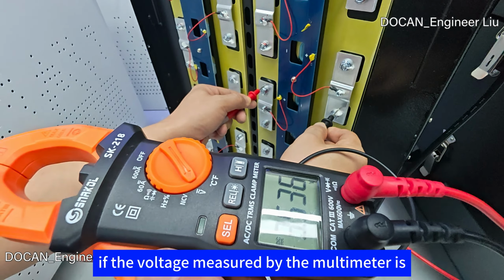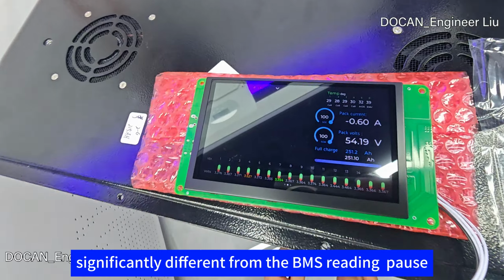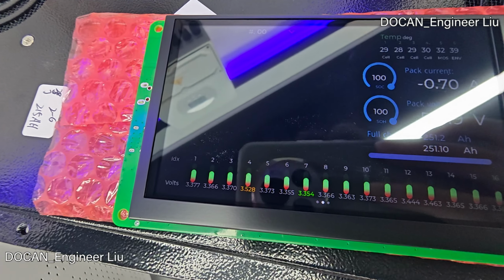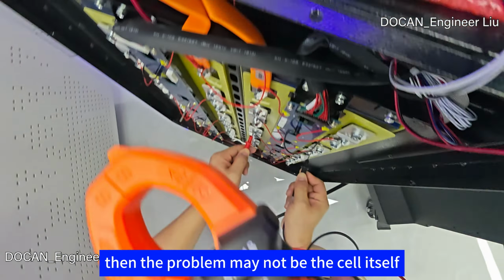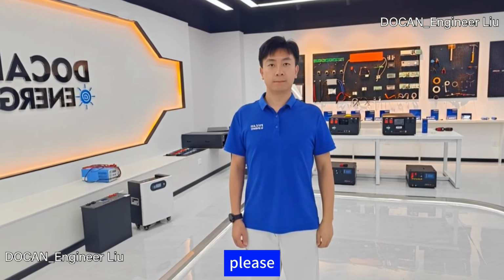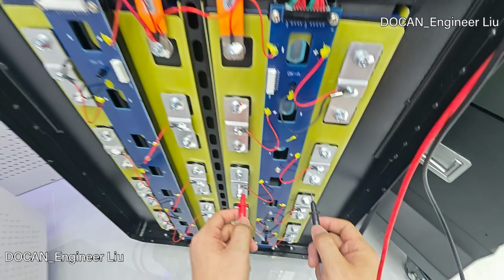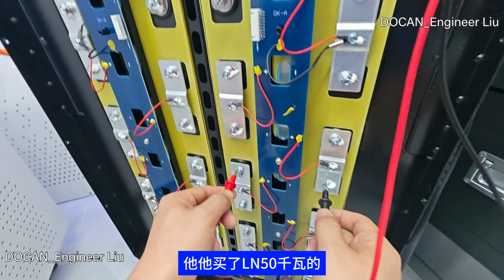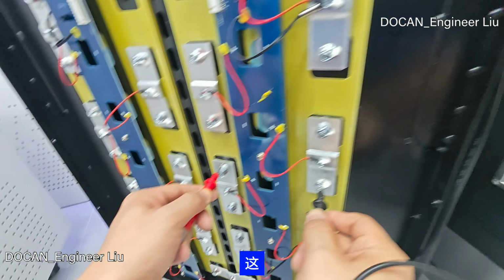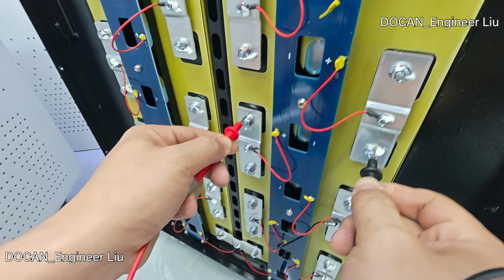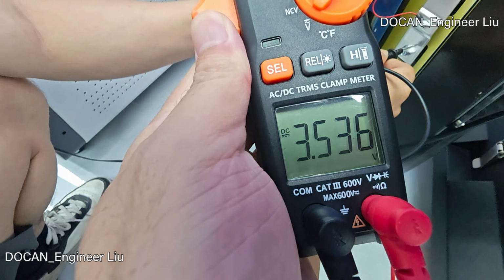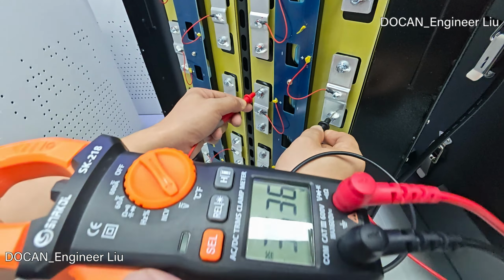If the voltage measured by the multimeter is significantly different from the BMS reading, then the problem may not be the cell itself—please move to step 2. However, if the multimeter reading is almost the same as the BMS display, this means the cells themselves may actually have an imbalance problem, and further balancing may be required.